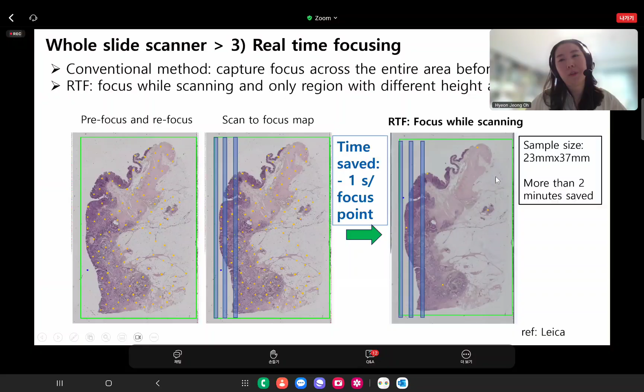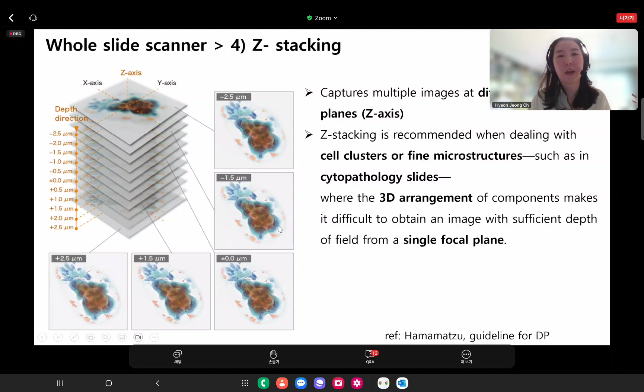And a new technique is real-time focusing. In the conventional method, a scanner captures focus across the entire area before scanning. But with real-time focusing, focus is done while scanning, and only regions with a different height are focused. So if you scan a sample size like that, you can save more than 2 minutes. The next technique is z-stacking. Z-stacking means capturing multiple images at different focal planes along the z-axis. It is recommended when dealing with cell clusters or fine microstructures such as cytopathology slides.